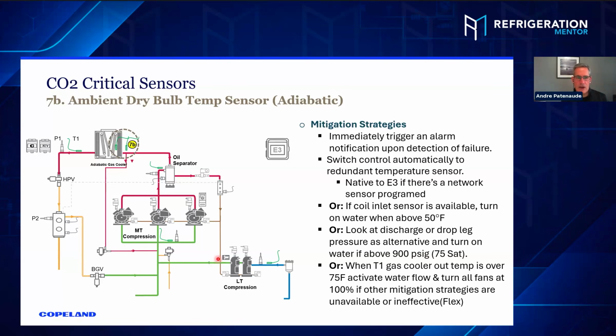So there is some mitigation around that sensor, 7B. Immediately trigger an alarm upon failure. If you have a redundant sensor, switch to it. But if you don't, and the coil inlet sensor is available, turn water on when it's above 50 degrees. So if 7B fails and 7A is above 50 degrees, the recommendation is you can turn the water on, just to limp along, so that if it gets warmer and warmer in the afternoon, you're going to have some protection.